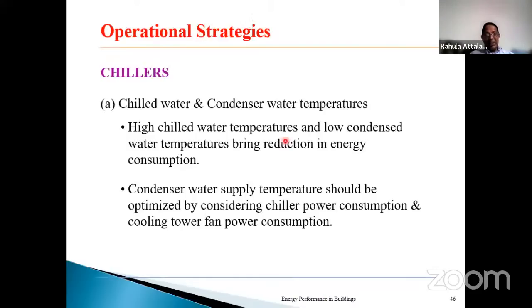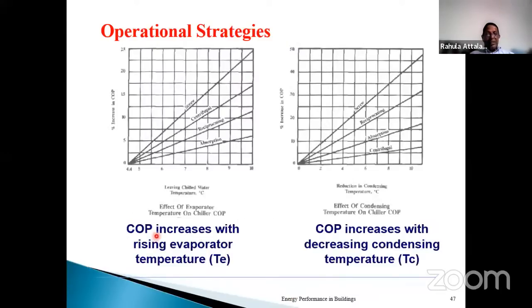Operational strategies. Here, condenser water supply temperature and the chill water temperature. This graph indicates how COP changes can take place by changing the chill water leaving temperature and reducing the condenser water temperature for different chiller types, screw chiller, centrifugal chiller, etc. For example, if you take the leaving chill water temperature and change it from 6 to 7 degrees, a change of 1 degree, for a screw chiller you can change the COP by this amount.